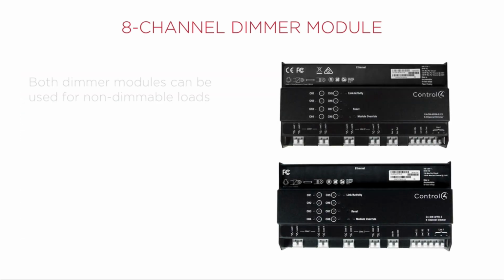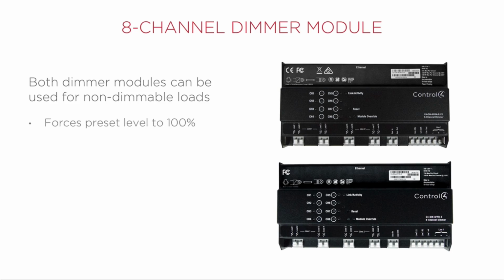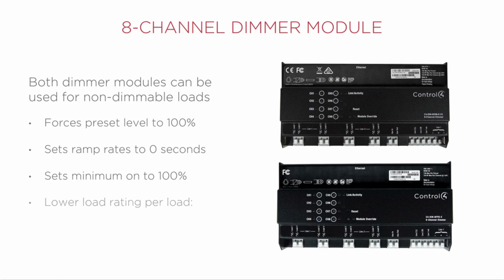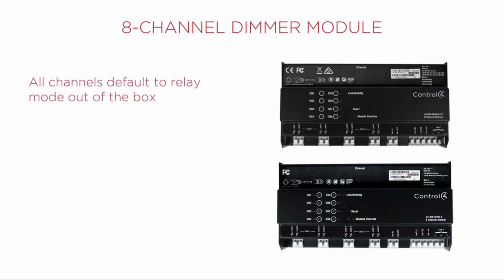Either module can also be used for non-dimmable loads. There is a forced preset level of 100% and forced ramp rate of 0 seconds. The minimum on is also set to 100%. There is a lower rating per load of 500 watts or 1/2 horsepower. Out of the box, all channels default to this mode. Dimmer properties are later set in Composer.